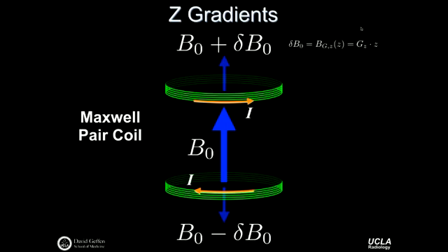And usually how we describe the effect of these fields is to say that the gradient has a particular amplitude, or the Z gradient in this case has a particular amplitude, and the effective field or field offset depends on the dot product of the gradient amplitude and the position. And there's a couple interesting consequences of this. One of them is that anytime you're at isocenter, if Z is 0, gradients don't do anything. So no matter what gradient you're turning on, of any magnitude, of any time course, of any behavior whatsoever, if your Z is 0, as it would be at isocenter, the Z gradient won't do anything. And that'll be true of the other gradients as well.